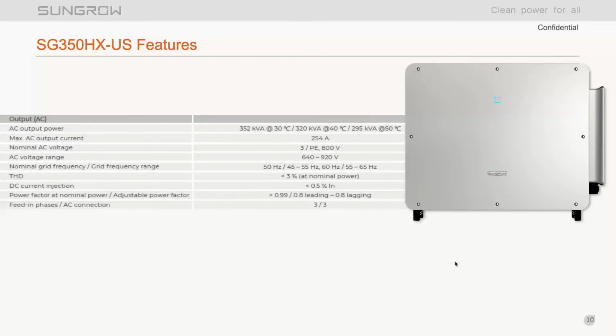Now moving to the AC side, the SG350HX is going to have a maximum AC output power of 352 kVA at 30 degrees C. And then we have a linear derate curve, so 320 kVA at 40 and 295 kVA at 50 degrees C. One of the improvements in the 350, which, to be honest, from an engineering standpoint, I didn't think would be easily achievable, but that's why our research and development department is the best in the industry. We were able to improve the cooling efficiencies of the new 350, so we can achieve greater CFM, which means greater cooling efficiency across the backplanes and the substrates of the IGBTs and the heat sinks, with less parasitic power used. So the efficiency of the 350, the total weighted efficiency, is even higher than the 250.